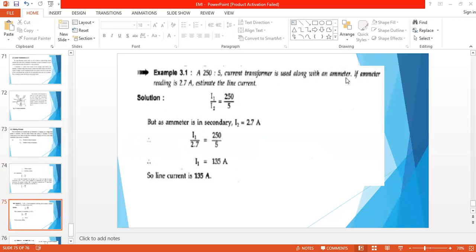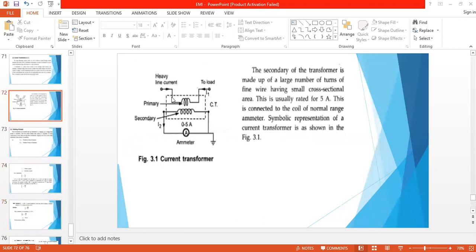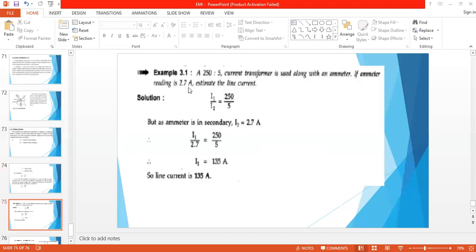As N2 is very high compared to N1, the ratio I1 by I2 is also very high for the current transformer. Such a current ratio indicates the range of the current transformer. For example, consider a 500:5 range current transformer, meaning it steps down 500 amperes to 5 amperes. For a 250:5 current transformer — if the ammeter reading is 2.7 amperes, the line current equals (250/5) × 2.7 = 135 amperes. So the line current is 135 amperes.